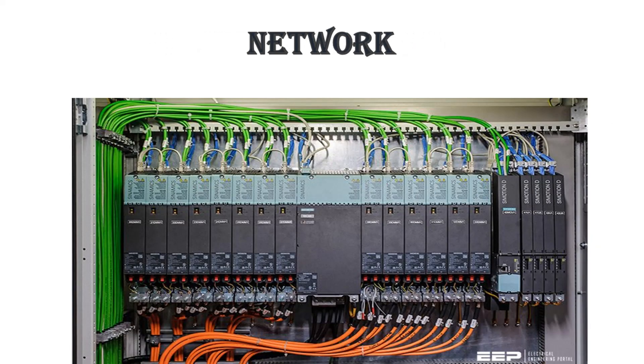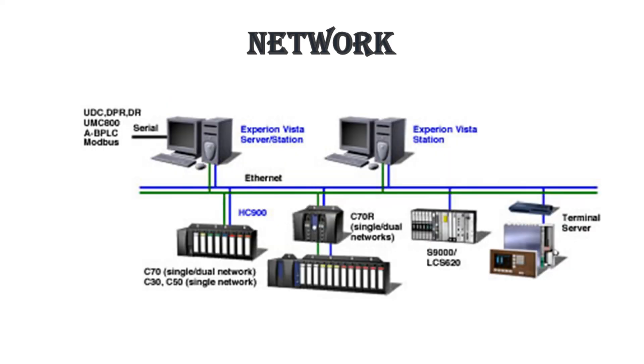The controllers execute control strategies to help optimize the process. The controllers are available in redundant and non-redundant configurations. The speed of execution of the control strategy determines the quality of control. The controllers are provided with a rich set of libraries for various algorithms such as PID, cascade, feed-forward, etc. The controller receives input from the channel of its connected input module, and similarly sends output to the configured channel of the output module to drive the final control element.